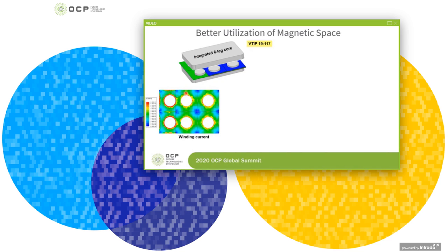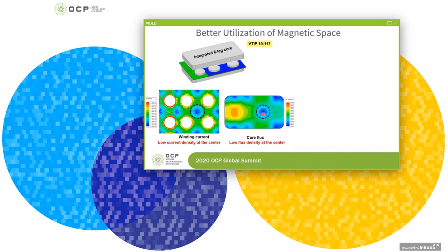This is the winding current. At the center between the 4 transformers, we have a small current density, which is basically an underutilized part of the footprint. Looking at the flux density in the core, we see a very small flux distribution at the center between the 4 transformers. So, regarding both flux and current, there is underutilization at the center.